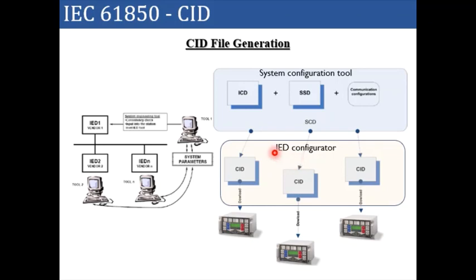Now this SCD file will be imported in an IED configurator, and then using the IED configurator, specific CID files will be generated which are specific to the SCD file which you have imported. So using this SCD file, you will create the specific CID file for a specific IED, and then these CID files will be imported into the respective IEDs. Now these IEDs are configured for the activities to be carried out in a particular substation.